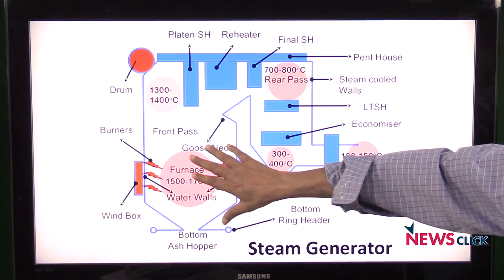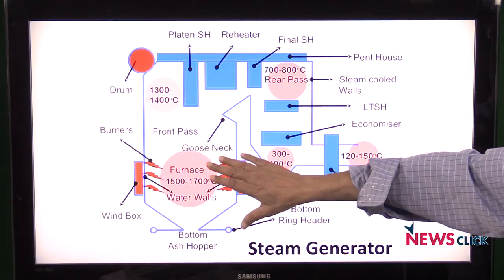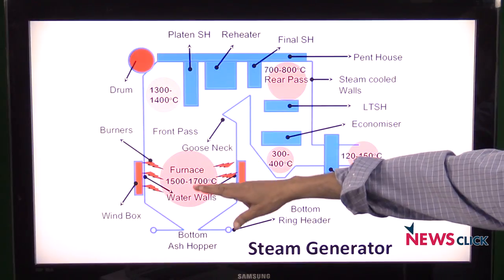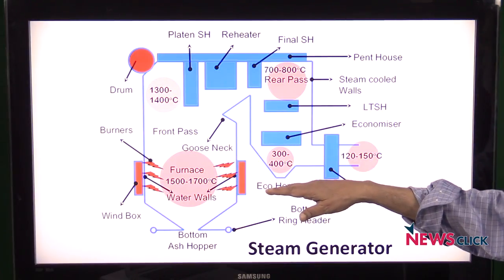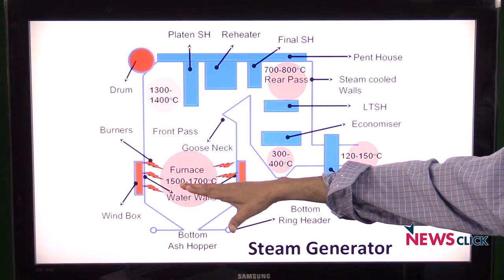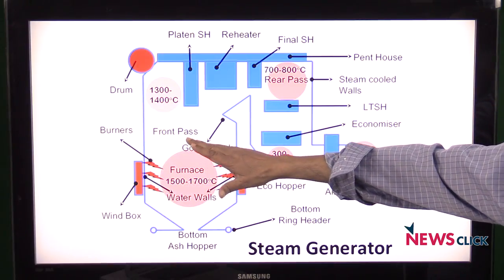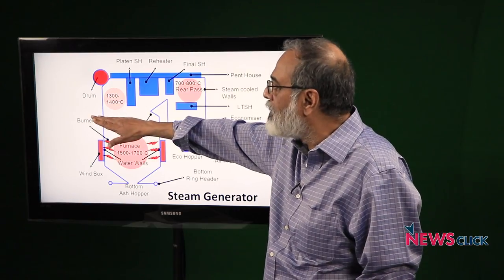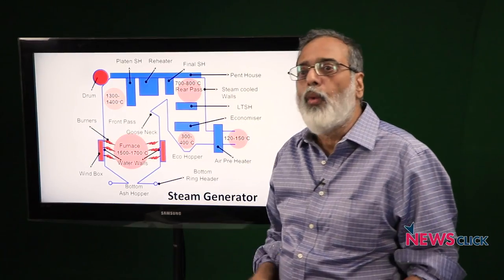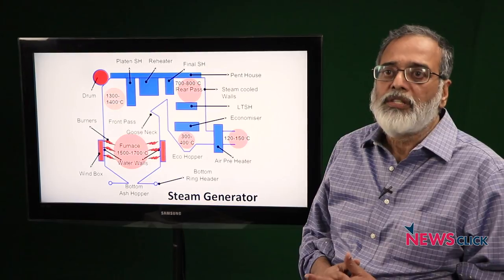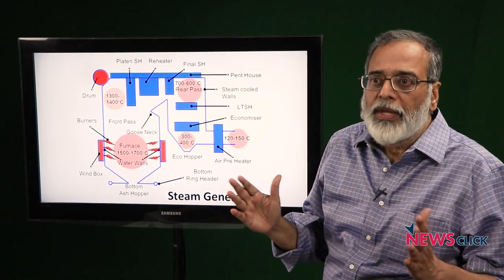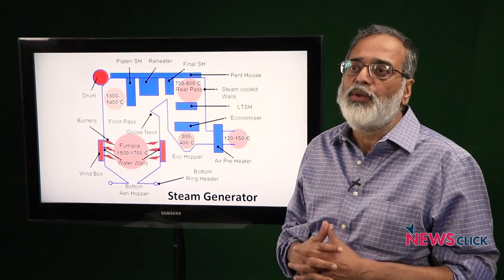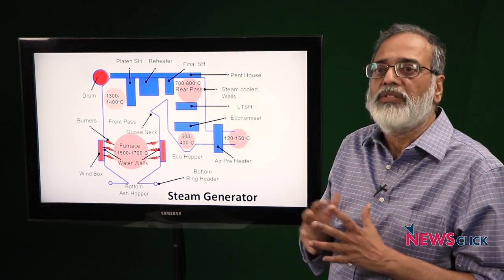The protection of the boiler due to high furnace pressure had been bypassed, so these pressure fluctuations did not trip the fuel. Fuel was still entering the boiler. That led at some point to an explosion in the boiler and at one point, one elevation corner seems to have actually cracked, leading to furnace gases exiting into the atmosphere and causing a lot of damage.